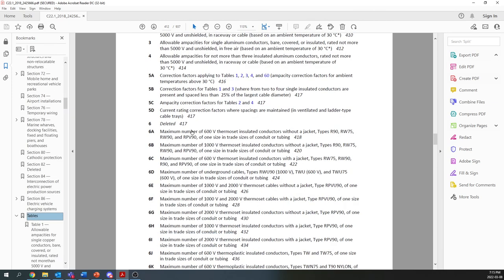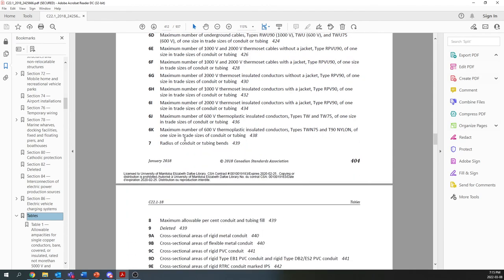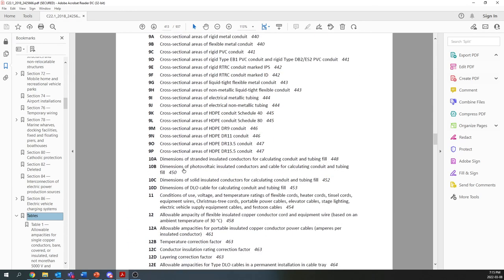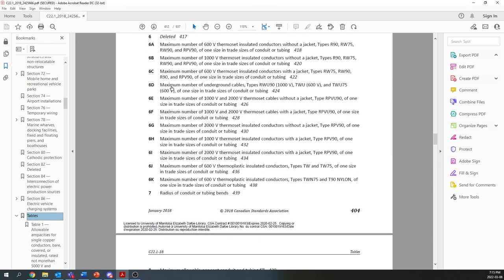So the next step is to see what size of conduit we need. That's the other thing that I've asked for. I'll make a comment here that the calculation for conduit fill, the amount of wires going into a conduit, has changed pretty significantly between the 2018 and the 2021 code. It's now a more general calculation, but it takes a little bit longer. But we'll do it the old way because it's actually a little bit easier.